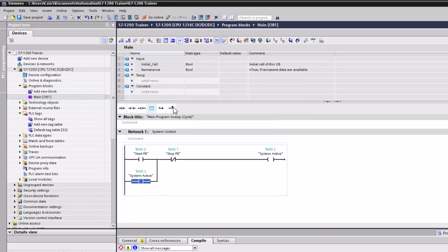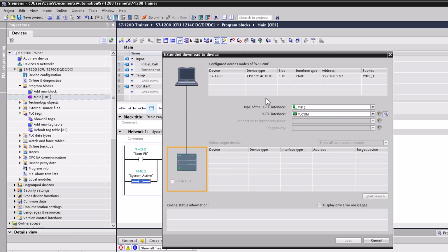We will actually show you how to have connectivity in this process right here. This again is going to come back and choose the protocol that we're using. You're going to choose the interface that you're going to interface with. On my computer, I'm using the Intel Pro. So that's my connection. And then we're going to connect to the connection that we told the processor it was before, which is the PN-IE_1. Okay. So this is that Profinet, right?